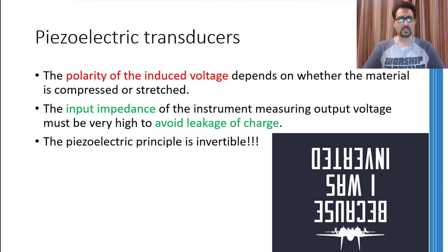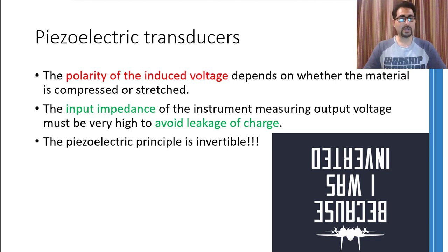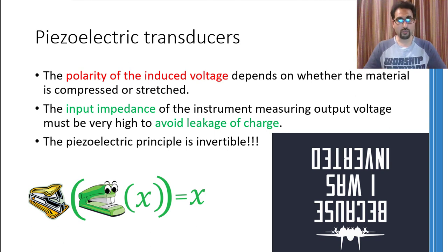Not only compressive force can generate voltages out of a piezoelectric material, but a force stretching the material will result in a negative polarity voltage. Therefore, it can be readily identified whether the force is tensile or compressive. The charge generated by these piezoelectric materials is not of a large magnitude. Therefore, the instruments used to measure the output voltage should have a very high input impedance, so that the small charge generated by these materials cannot leak and get consumed in the attached circuitry. As a final point, the piezoelectric principle is invertible — if you apply force, they will generate a charge; and if you apply a charge, they will generate a force. Therefore, these materials can not only receive ultrasounds but are frequently used as a source of ultrasound as well.